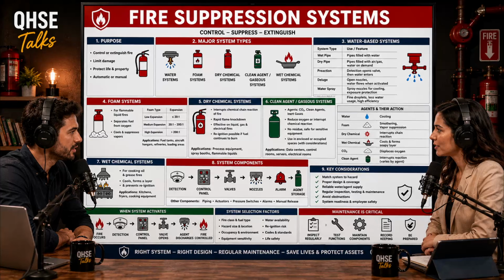I want you to break down the physics there, because my layman's instinct might be that without those acoustic panels blocking the way, the heat would just shoot straight up to the sprinklers and activate them faster. It's a common misconception, but it's entirely about convective heat transfer. When a fire starts, the hot combustion gases rise in a vertical column called a fire plume. If you have a solid, flat ceiling, those hot gases travel up, hit the ceiling, and are forced to spread out horizontally in what we call a ceiling jet. So the heat mushrooms out and banks against the ceiling barrier. Yes, rapidly raising the temperature right where the sprinkler heads are located. The thermal element reaches 100 degrees quickly and activates.